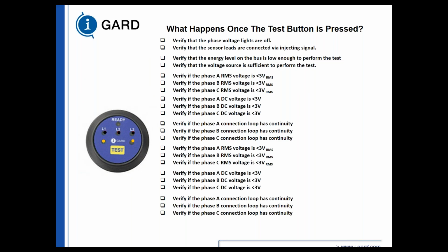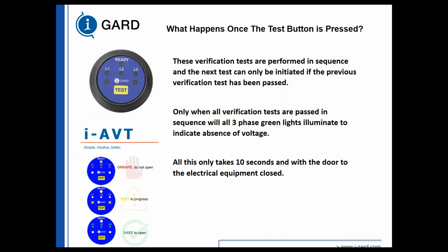And in real time, the way it happens is we go through all these procedures in 10 to 15 seconds and ensure that everything is less than 3 volts AC, DC twice. We check the continuity twice, and when that's done, you get 3 green LEDs, and you verify that the voltage is truly absent from that circuit. And we've checked the circuit to make sure that it's connected properly. We've checked the instrument to make sure it's functioning properly. And so you have an electrically safe work condition.